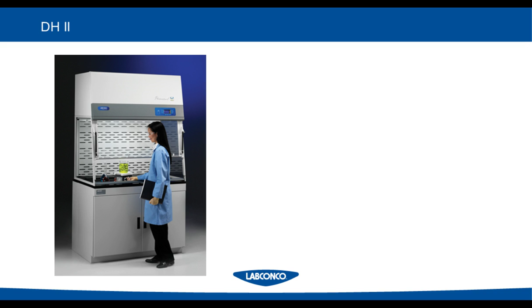Next, we have the DH2 hood, or ductless hood 2. This hood meets all of the DH1 requirements, plus it has different types of filters, like inorganic filters or ammonia filters, or different kinds of filters that you can order based on what your application requires. They can also handle manufacturer-approved toxic chemicals, often determined through a chemical assessment form. Another thing about the DH2 is that they do have a chemical sensor to detect breakthrough, unlike the DH1.